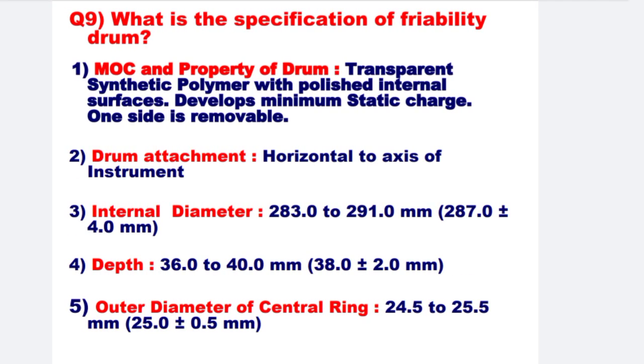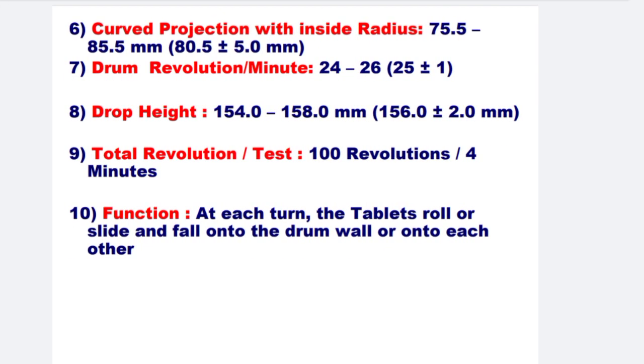Next: What is the specification of the friability drum? Number 1: MOC and property of drum — transparent synthetic polymers with polished internal surfaces, develops minimum static charge, one side is removable. Number 2: drum attachment — horizontal to the axis of instrument. Number 3: internal diameter — 283 to 291 mm. Number 4: depth — 36 to 40 mm. Number 5: outer diameter of central ring — 24.5 to 25.5 mm. Number 6: curved projection with inside radius — 75.5 to 85.5 mm.